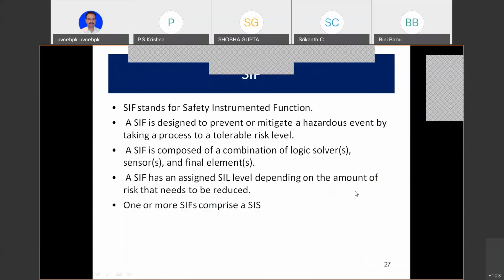And a SIF is almost like a safety instrument system, but it does one function. This function is protecting the furnace. The other one may be protecting a level, or another one may be protecting a boiler. So each one is doing a different function, but all of them may be operating on one super duper PLC, which is the SIS. That's one thing you have to understand.